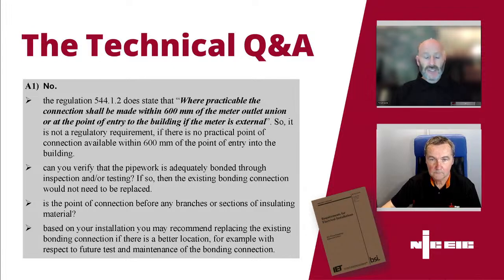So it's a case of, like you said, apply your engineering judgments, think of the foresight of installation, speak to the client, ask them what's going to be done around the area, and if it's going to get closed up, that connection point is not going to be good. For access reasons and testing purposes, 600mm from the union part. So yeah, apply engineering judgment, make sure you can do your testing. Any concerns on the certificate, document it in part 3, comments on existing installation, and apply due diligence.